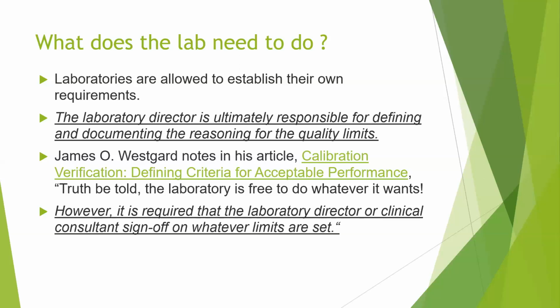In fact, Dr. James Westgard, who is undisputedly the father of modern quality assurance in the laboratory, has stated in his article, called Calibration Verification, Defining Criteria for Acceptable Performance, and this is very important, that truth be told, the laboratory is free to do whatever it wants. So no one is compelling you to set a particular limit. But it is important that you have a rationale for it and document the reason for that. And the lab director or the clinical consultant should sign off on whatever limits are set for your own acceptable error guidelines or your quality goals.